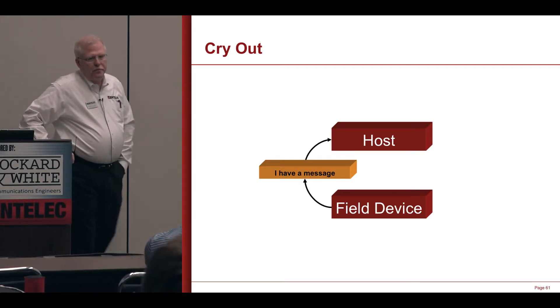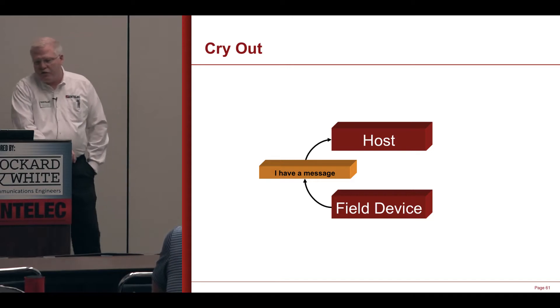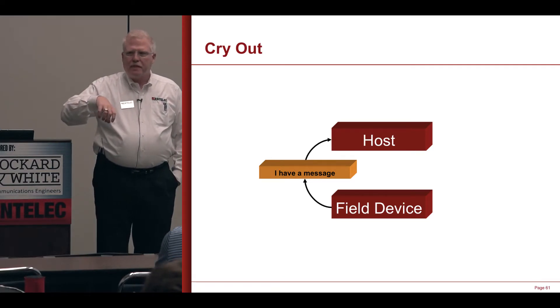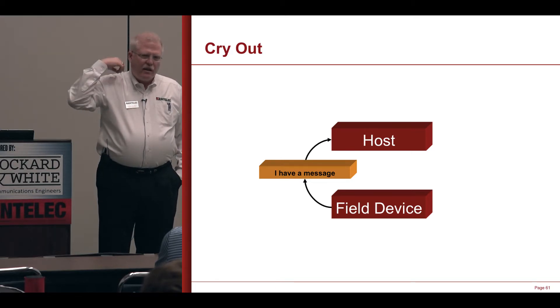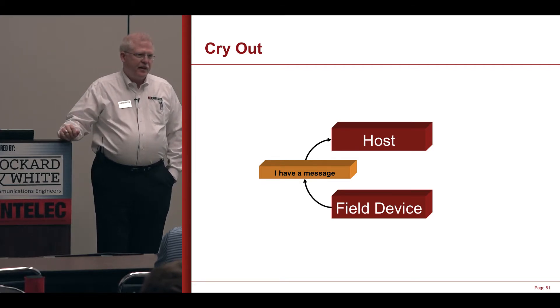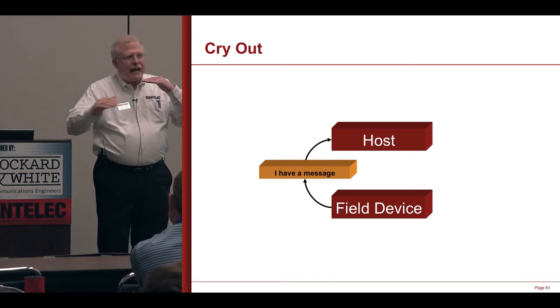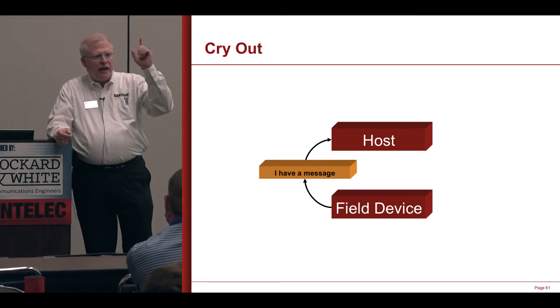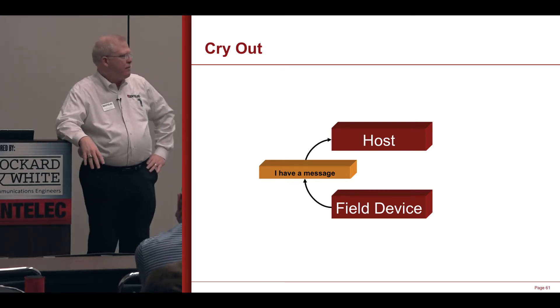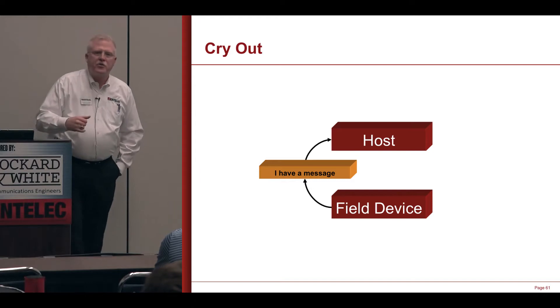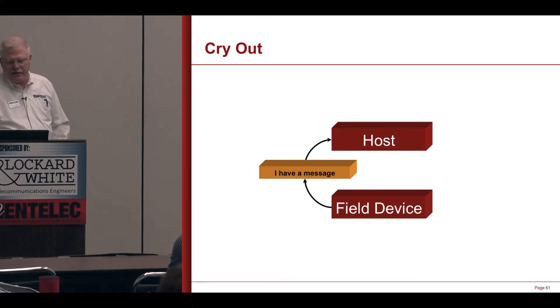The other idea is CRYOUT. The Fisher ROC has this, and many other devices have it. In poll response protocols, the host is the only one that can talk — he issues a poll and says, 'RTU100, I need these addresses.' What CRYOUT does is it allows the remote device to say, 'Hey, Mr. Host, I have something you need to know about,' and then the host will put that device to the top of the queue and poll it next. This has to be supported in both the field device and the host. CRYOUT is really handy for things like a critical upset — for example, over-pressuring the inlet of a gas plant or high fluids at the inlet of a gas plant.